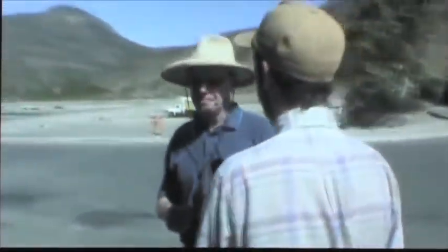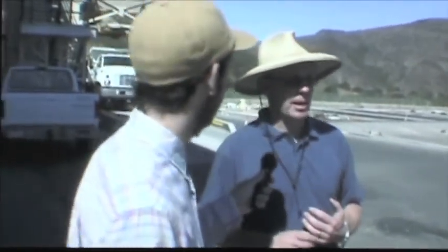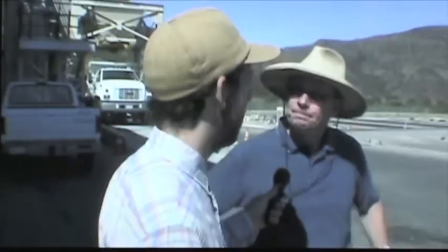One of the things that we've done is we've always been on an interruptible rate. And what that does is saves the city about $250,000 a year by our ability to turn those on in the event Edison comes to us and says, hey, we're running short of electricity. That happens very rarely, but it's been a great deal for everybody involved, because EPA requires us to have the generators here anyway. Right. So on those rare occasions in which we're able to go off grid, it helps Edison, and certainly the citizens pay less for electricity because of it. Wow.